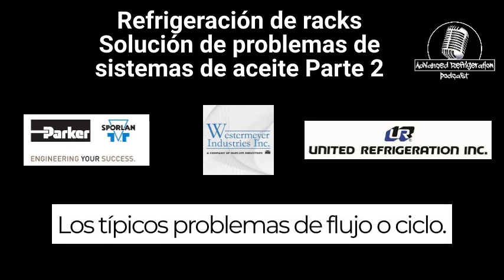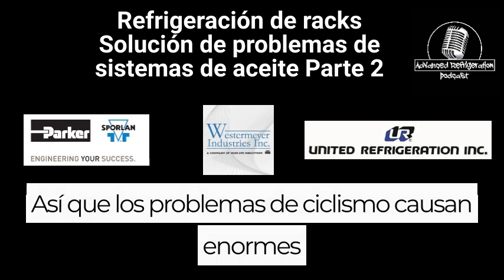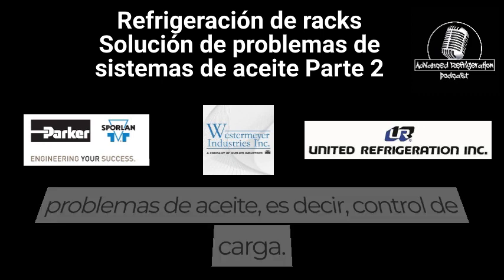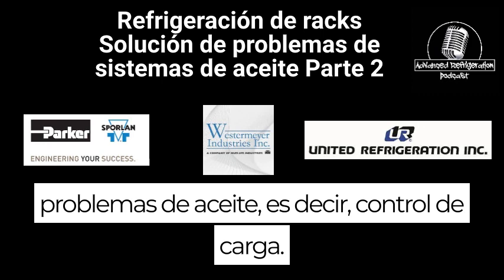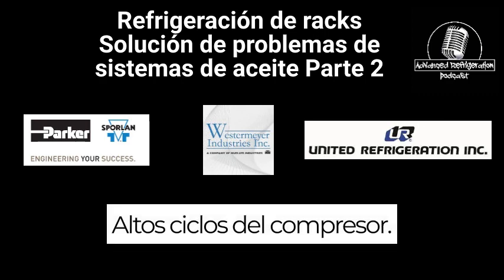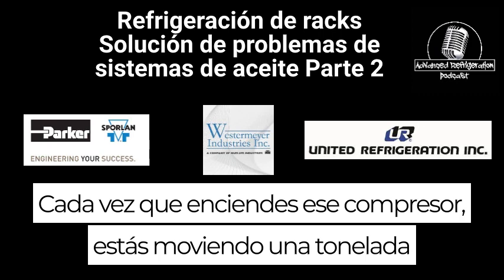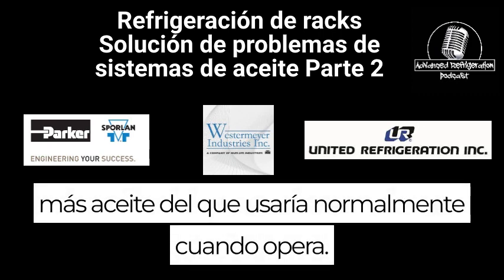The typical blow-by or cycling issues. So, cycling issues cause huge oil problems. Meaning load control: you have poor load control, high compressor cycles. Every time you start that compressor, you're moving a ton more oil than you would normally when you operate.